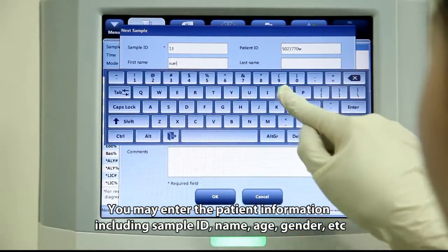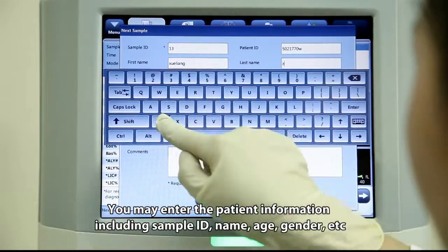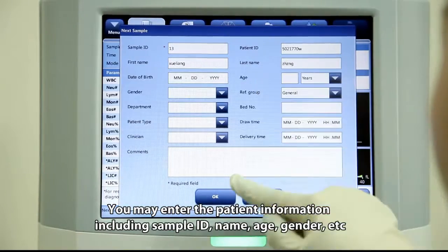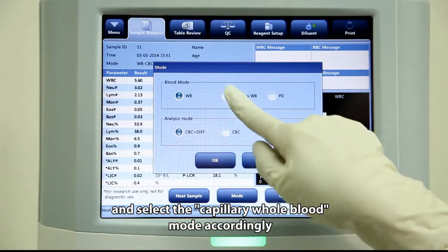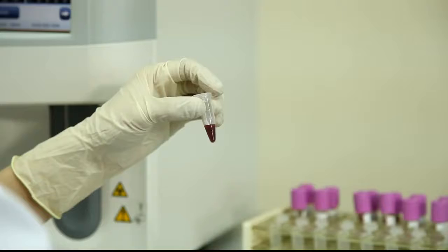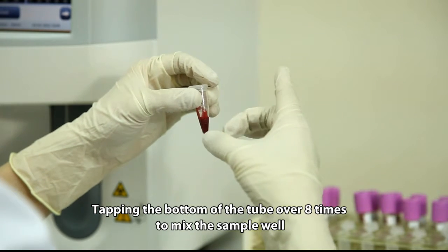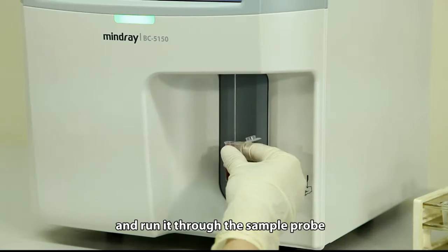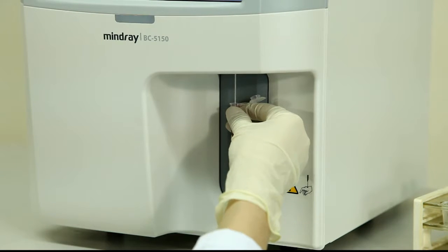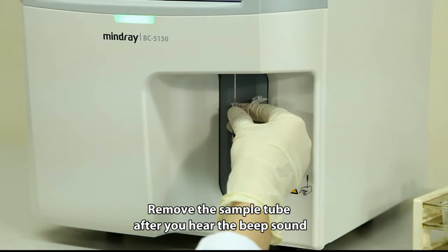You may enter the patient information including sample ID, name, age, gender, etc. and select the capillary whole blood mode accordingly. Tap the bottom of the tube over 8 times to mix the sample well and run it through the sample probe. Remove the sample tube after you hear the beep sound.